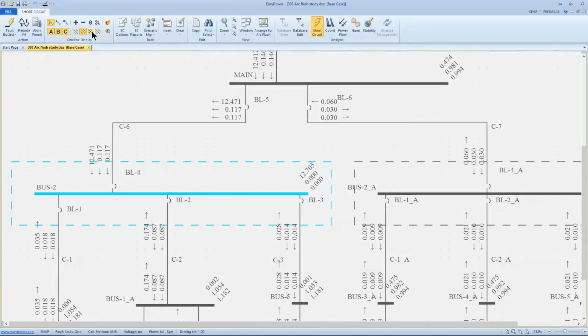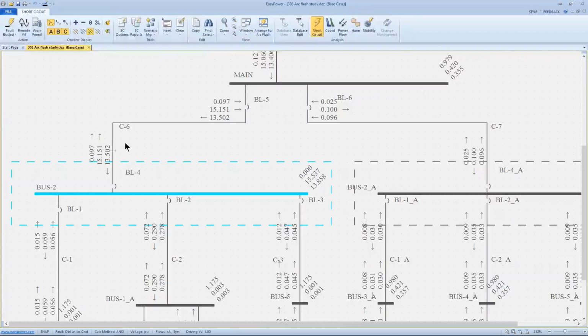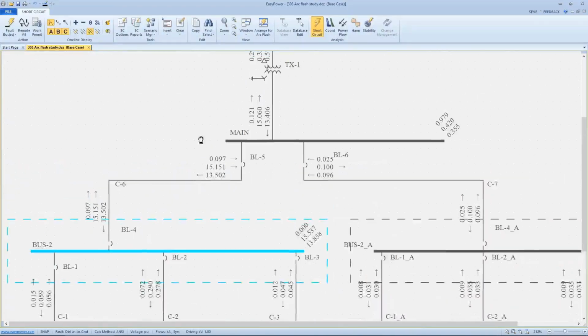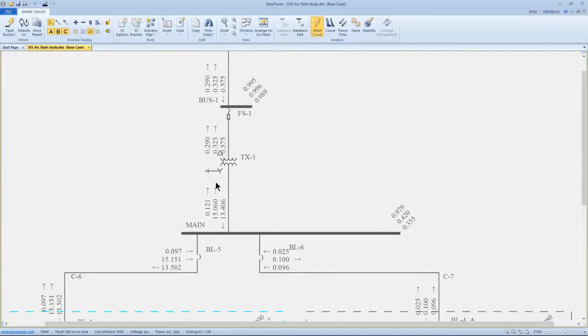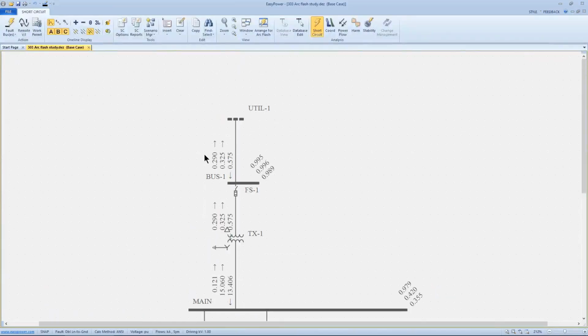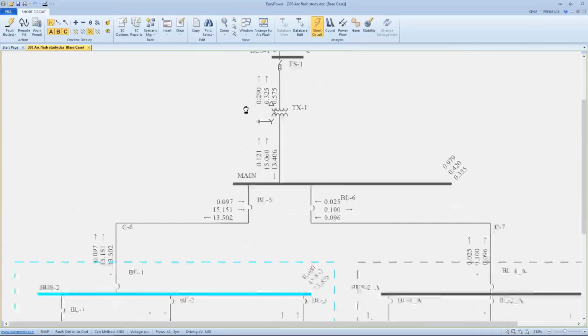And then another asymmetric fault would be a double line to ground. And again, the two high current phases would be the ones that are faulted to ground into each other. The significance here is that when we look at the grounded part of the system, sure enough, we have relatively high current in the two phases. And if we look at the ungrounded part of the system, we have an imbalance in the phases because the shorted phase will have the higher results, and then the ground current is effectively not going to show up as a standalone phase.